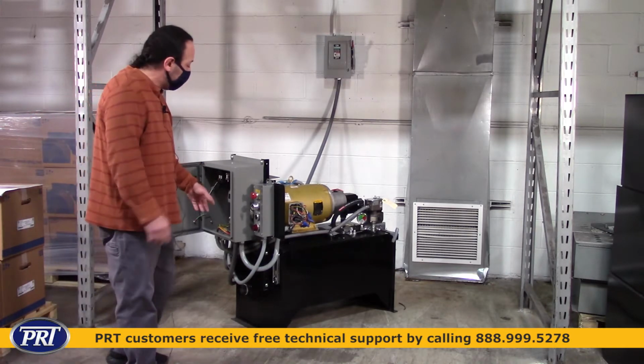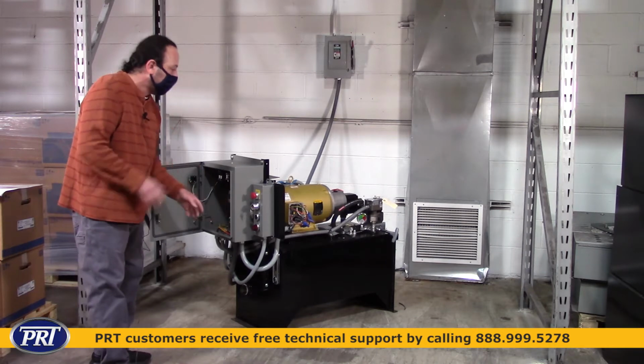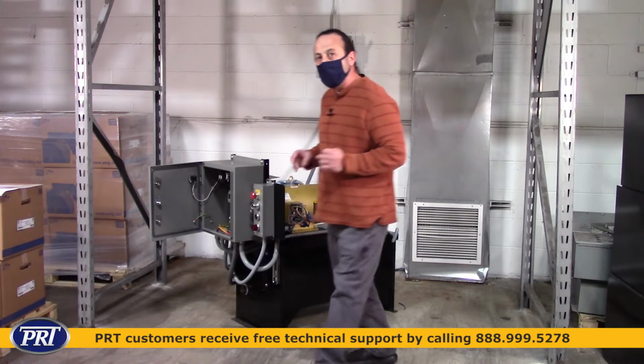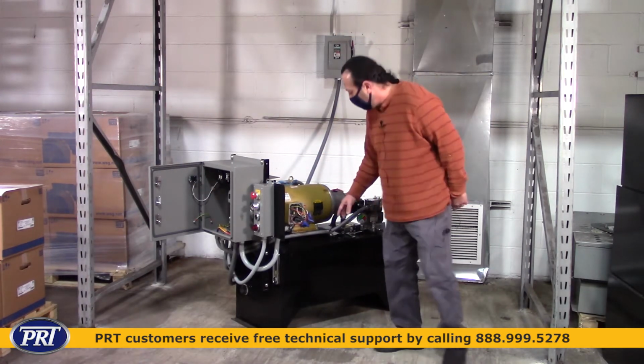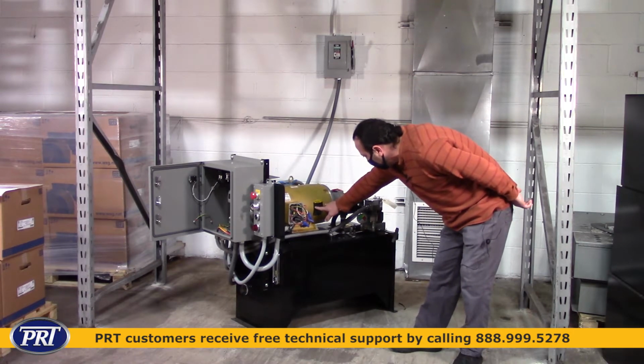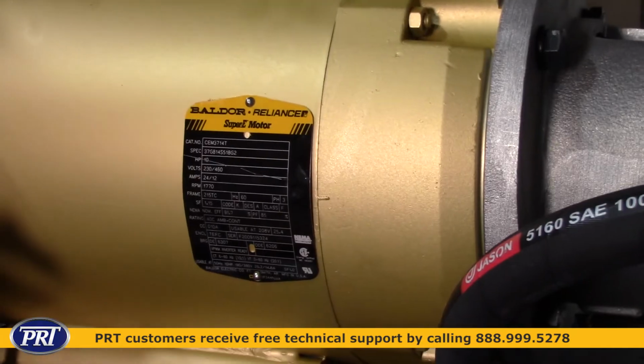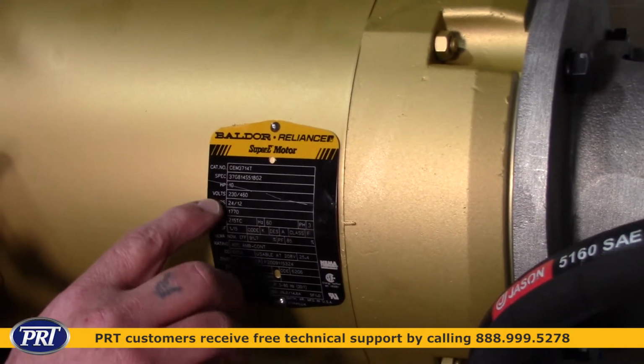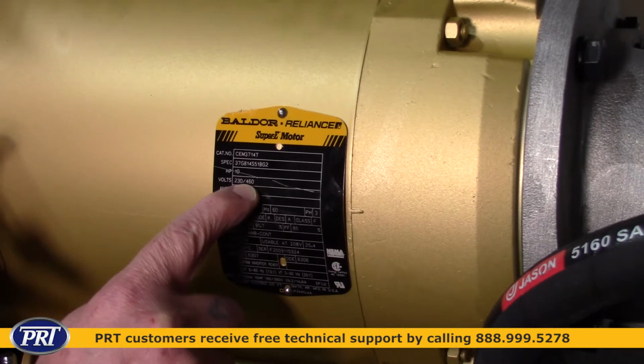And then the last thing you've got to do is set the overloads down here for the correct amperage per the motor. Now, where you get that information is you would look down here at the tag. There's a line that says volts, and then there's a line that says amps. All right, now the two lines that you're looking for, your voltage and your amperage, are right here. This is your volts, 230, 460.